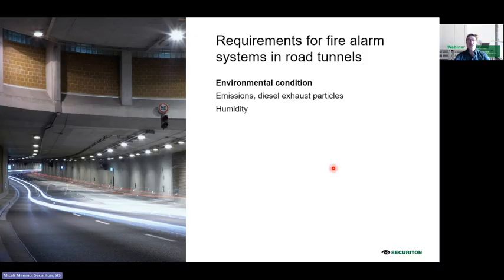So this is always changing because the tunnel is also open, so we always have air entering, and this change of humidity may also be an impact of the different systems installed in a tunnel. Then depending on the location of the tunnel, we may also have road salt mist, especially in regions where they have a winter with snow, and you have to prepare the roads again, avoiding ice on the roads.